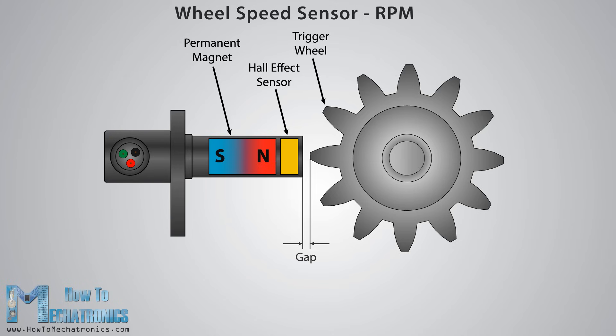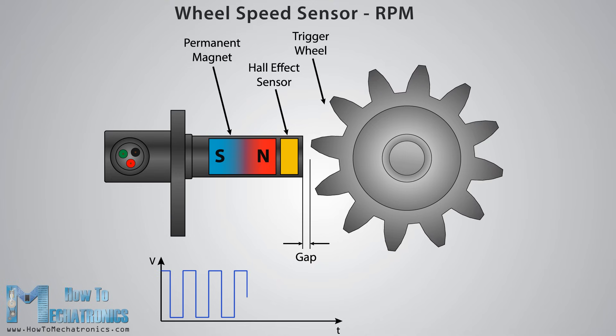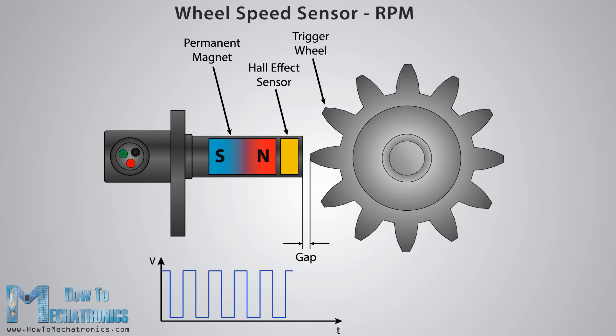The gap between the sensor and the teeth of the disc is very small so each time a tooth passes near the sensor it changes the surrounding magnetic field which will cause the output of the sensor to go either high or low. So the output of the sensor is a square wave signal which can be easily used for calculating the RPM of the rotating shaft.